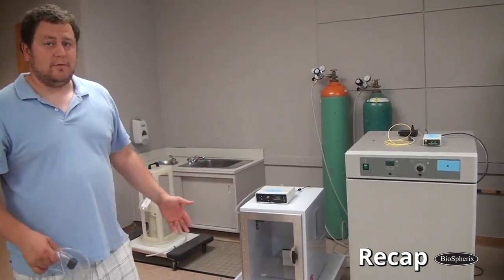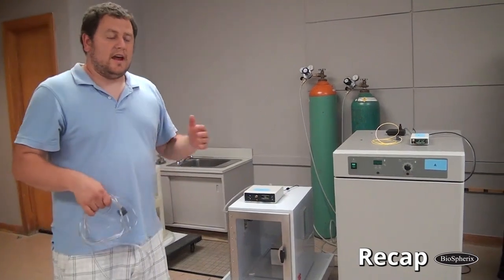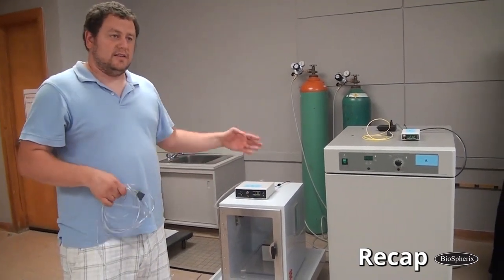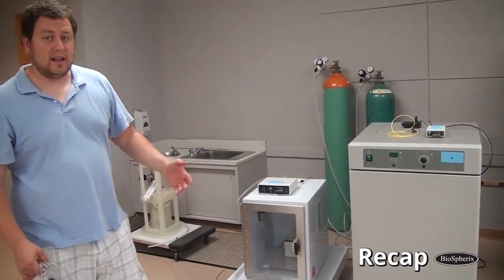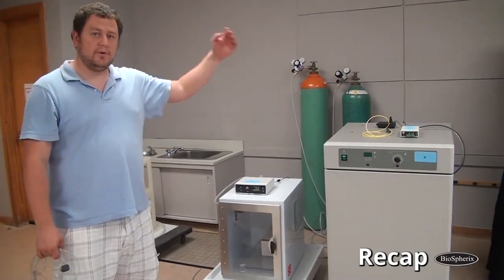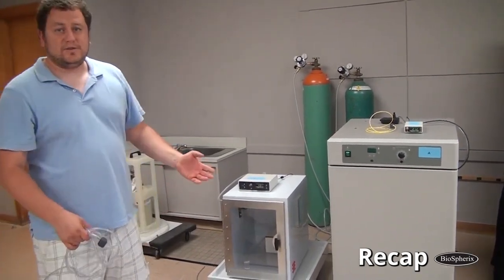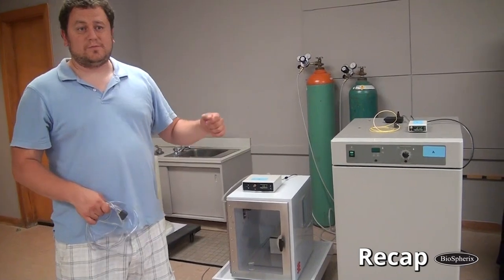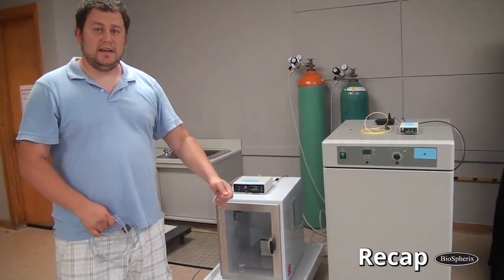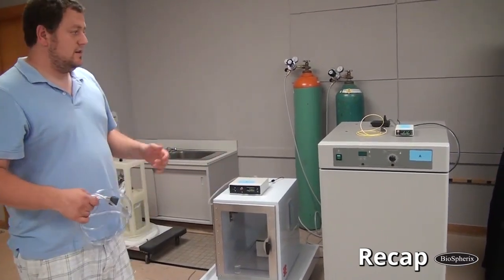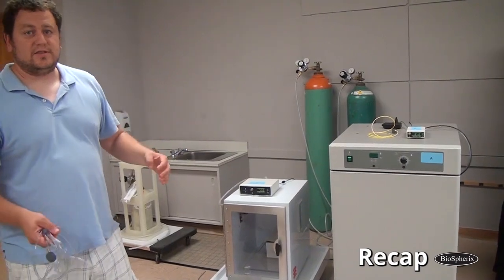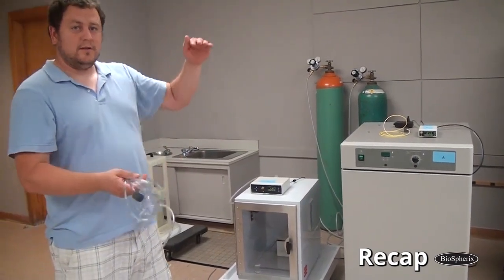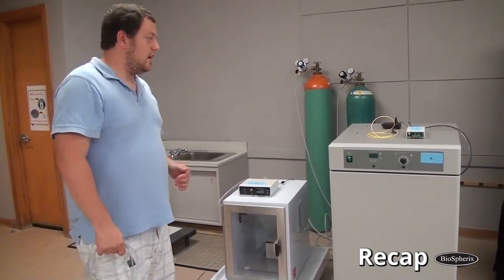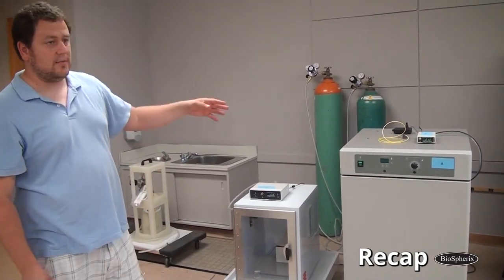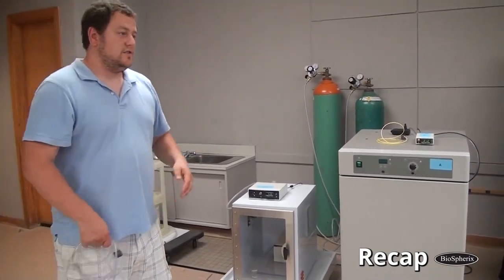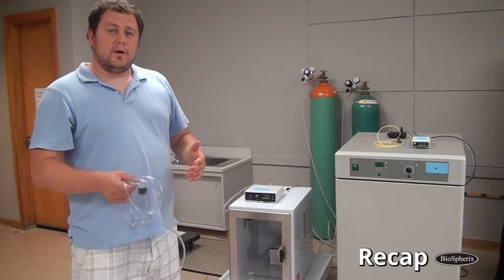Sensors have a lifespan of about 2 years, so at around that point it's going to get difficult to calibrate. You're going to see that span number jump quite a lot. I always recommend keeping track of that span number and the change that you make each time you calibrate. That's going to tell you when your sensor's starting to age, when you see those big jumps in span. At the beginning I said I would talk about the coefficients a little bit, just to give you an idea.